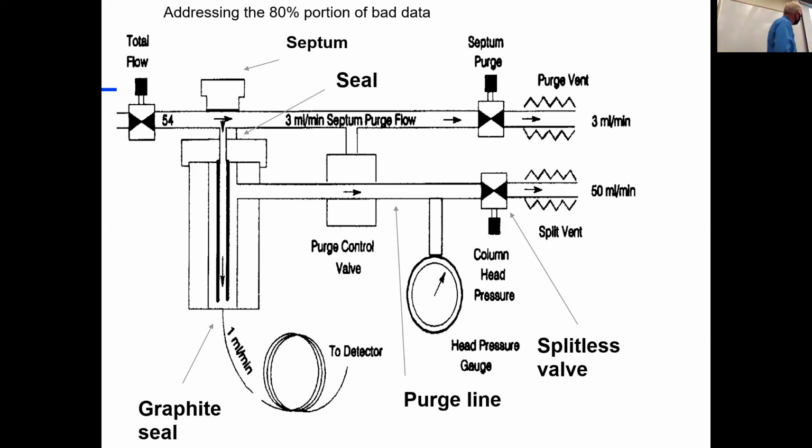Oh, there's a mention of purge line. I guess that's an addition on here. Here we go. That shouldn't be plugged. There have been occasions when it has been plugged. So again, another place, you make sure the gas is coming out as it should.